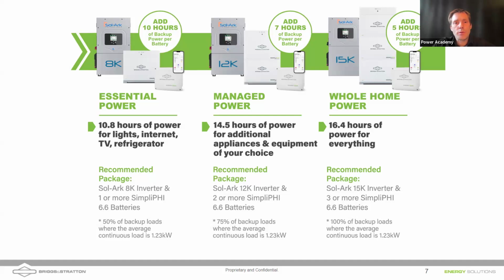And then the other two inverters that are shown there are for partial home backup systems. The 8K, typically we'll see customers use that for smaller selective backup. So we're calling that essential power. And you're looking at backing up maybe 50% of the loads in the house. You're going to back up the refrigerator, you're going to back up the lighting, the communication system, but you might leave off the electric water heater, the electric dryer, those kind of things.